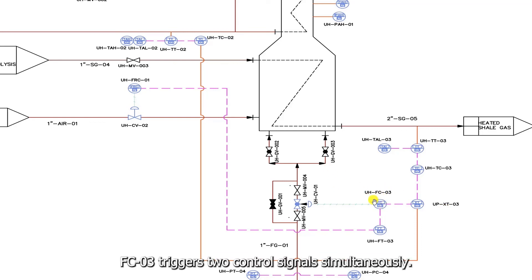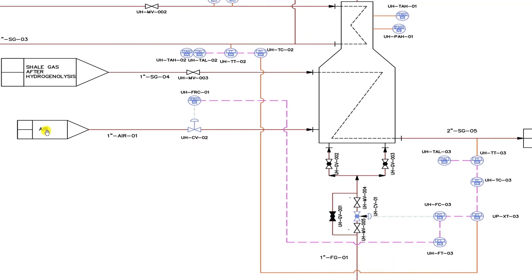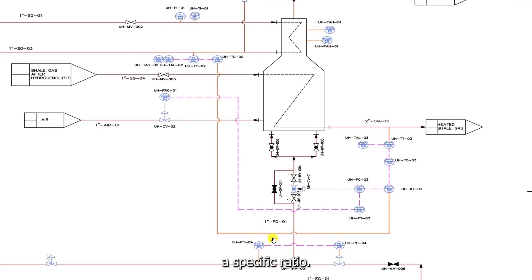The flow controller FC-03 triggers two control signals simultaneously. The first control signal is pneumatic. It acts on the fuel gas control valve CV-01 to adjust the flow of gas to the burners. The second control signal is electrical. It serves as input to the flow recording controller FRC-01, which converts it to a pneumatic signal to act on the air control valve CV-02 to adjust the flow of air admitted to the burners. This control setting forces the airflow to follow the gas flow according to a specific ratio.